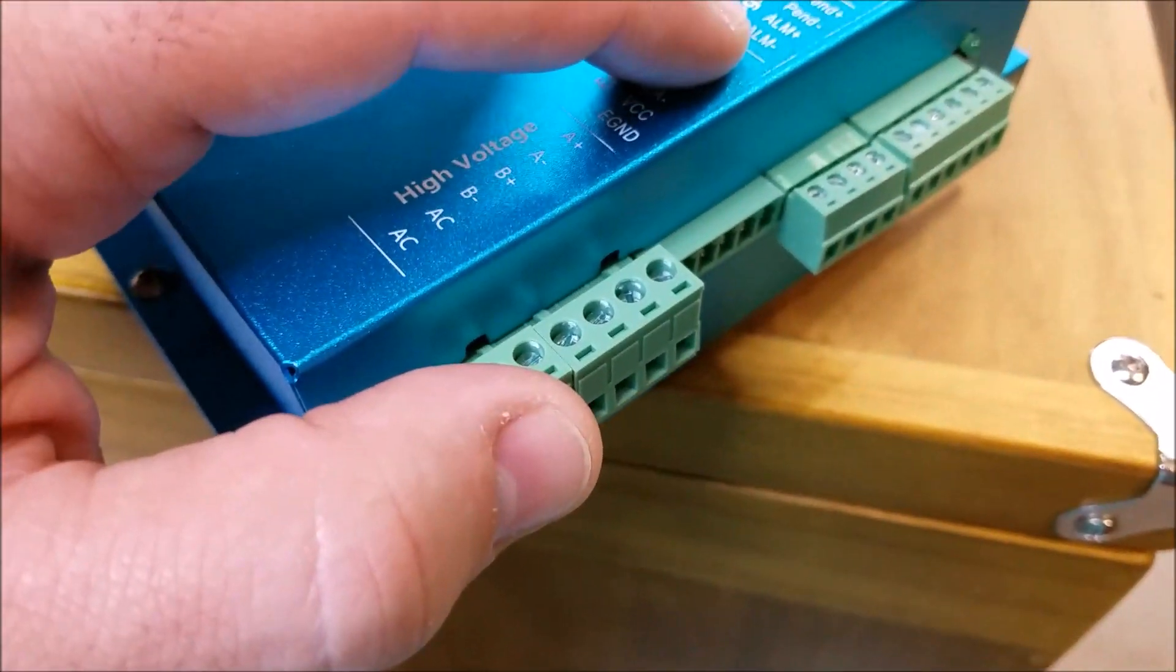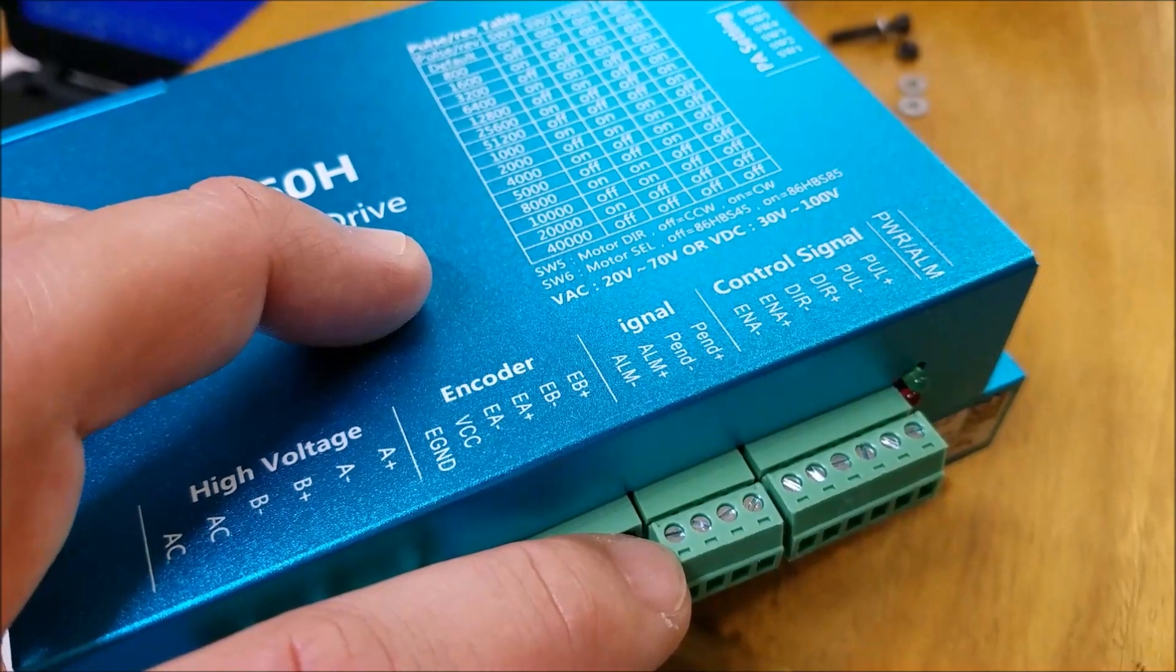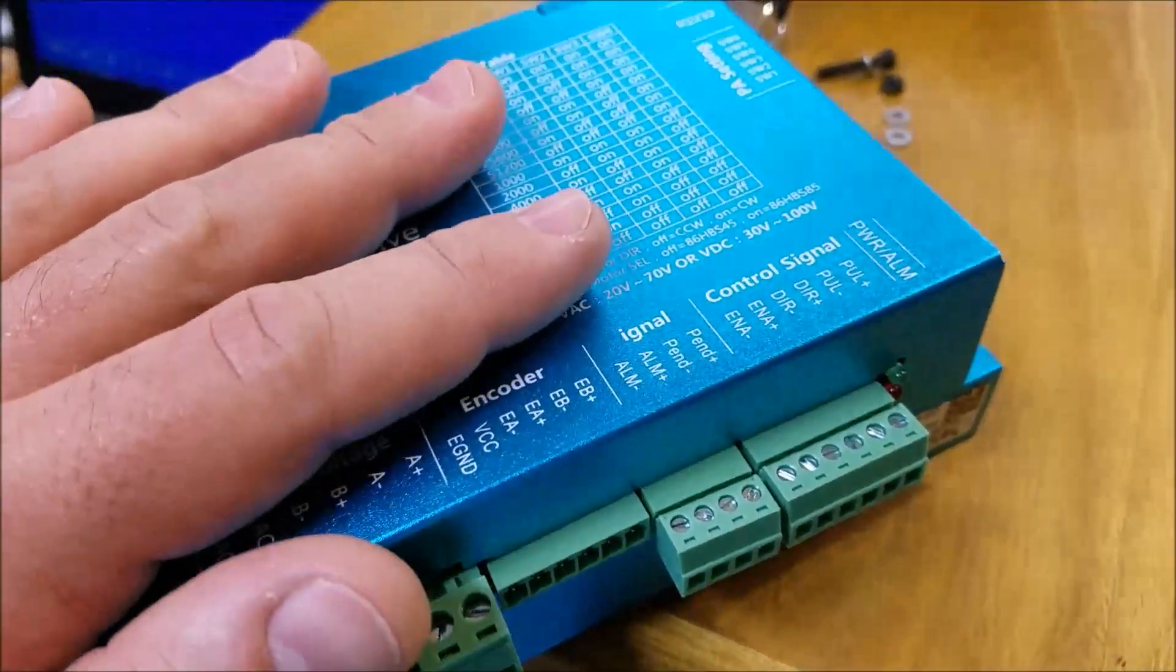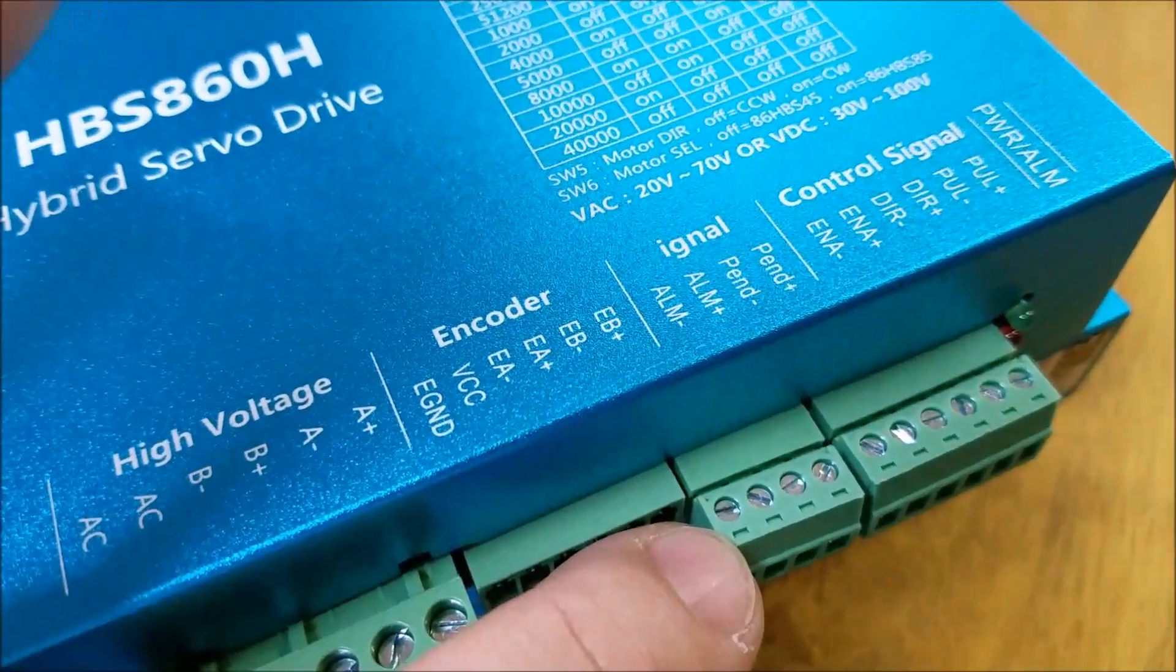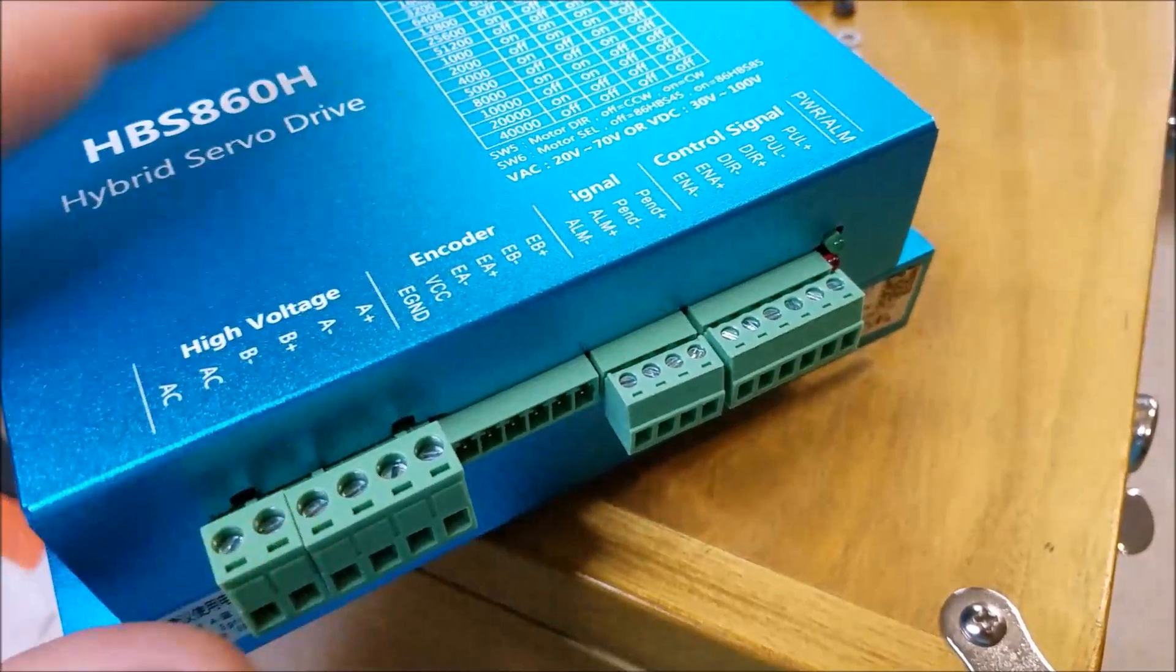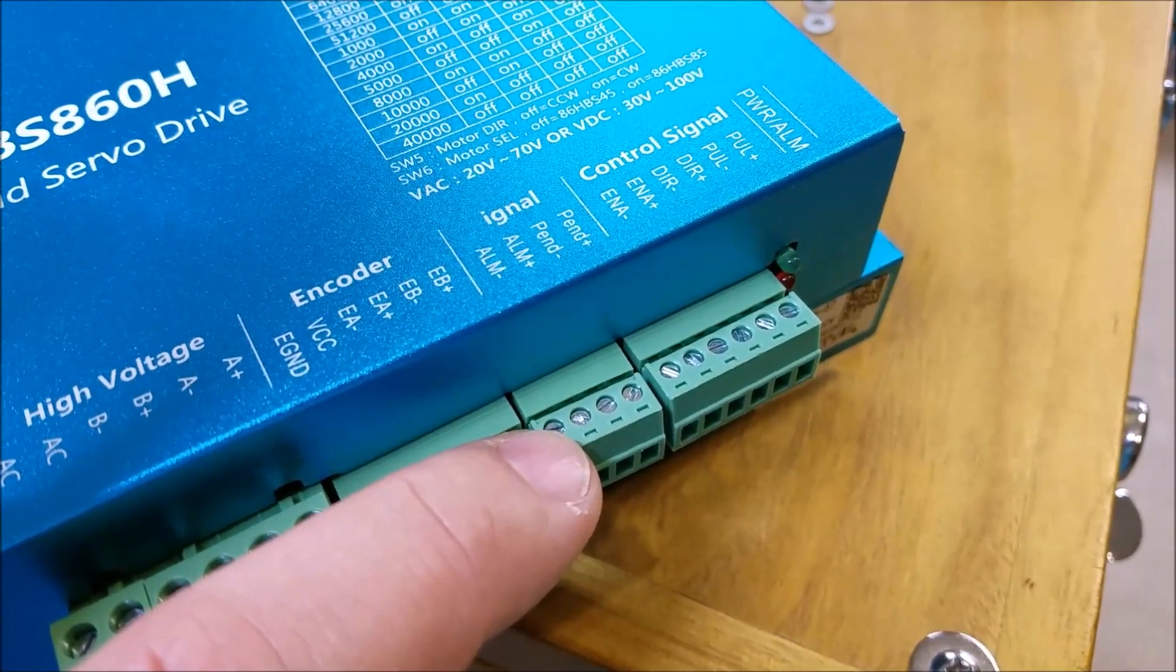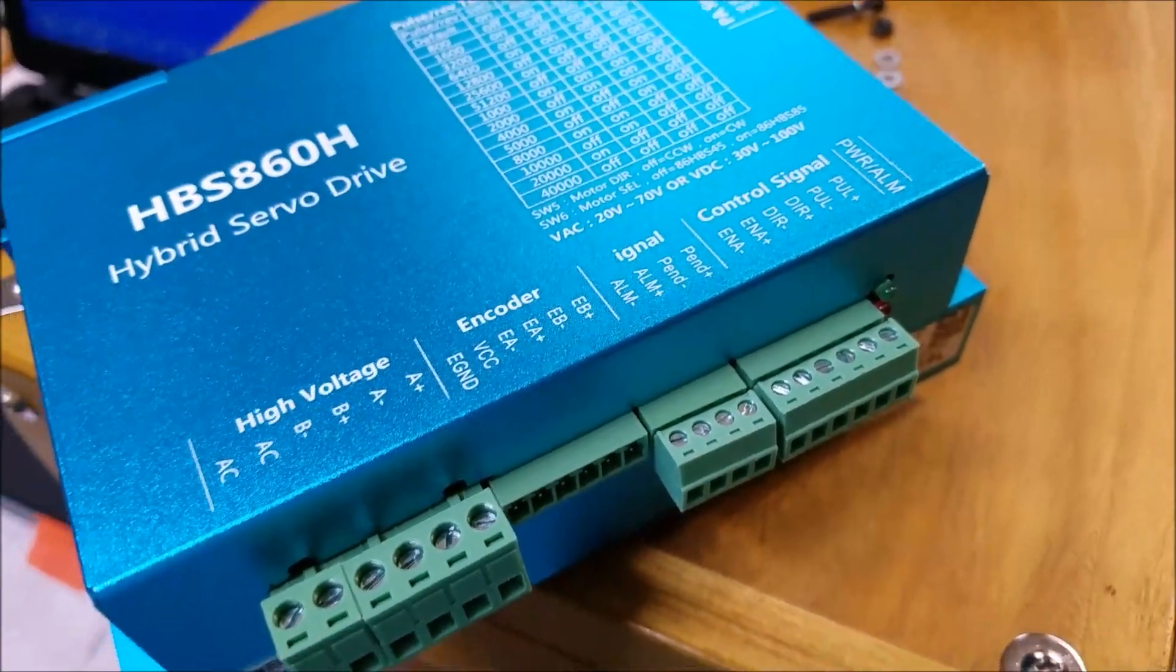This output, as far as I can tell, ships from the factory as a normally open connection. So that means if the drive is happy and everything's good, alarm minus and alarm positive are open. So the switch is open, so to speak. If something goes haywire and it's unhappy, then alarm plus and minus close. So you can imagine the switch closes. So when everything's good, it's open. If there's an issue, it closes.